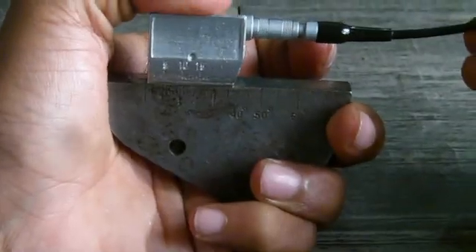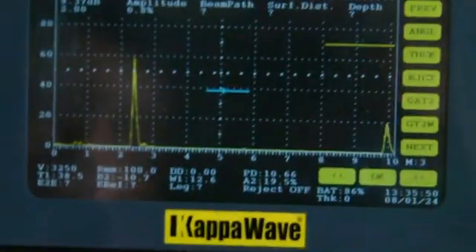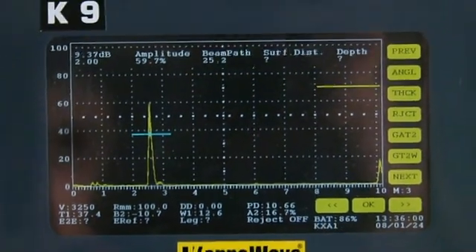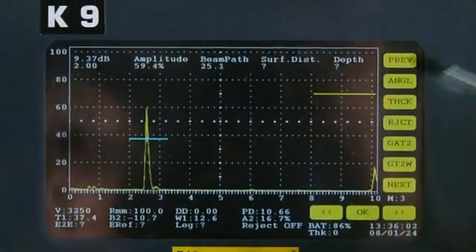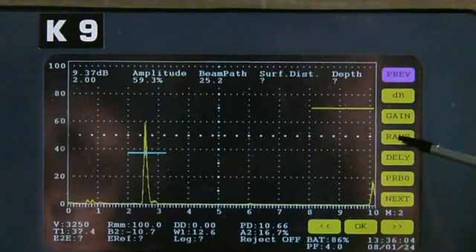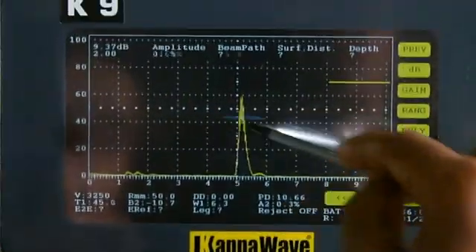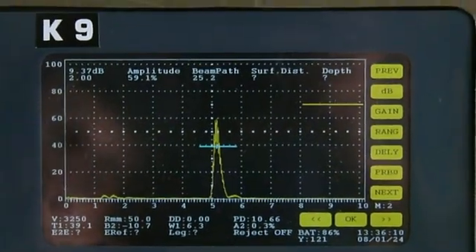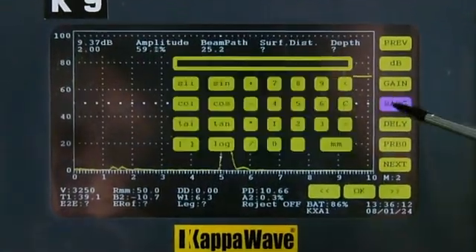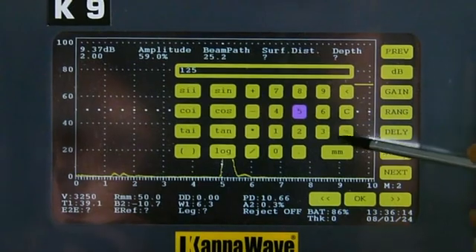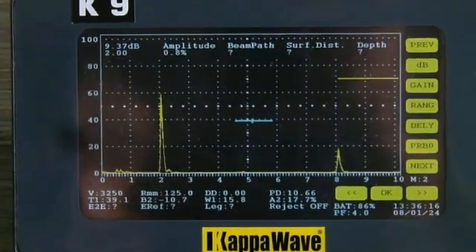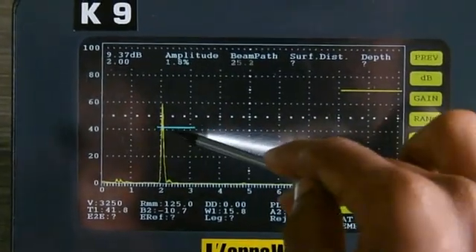Once the zero is correctly set, then you may change the range as desired. For example, from 100mm, you may change it to something like 50mm, or 125mm, or 200, 250mm, whatever.